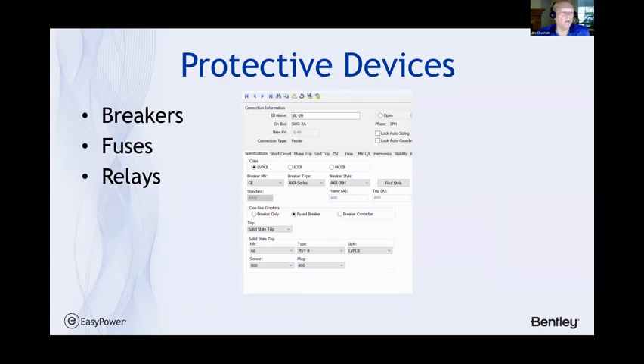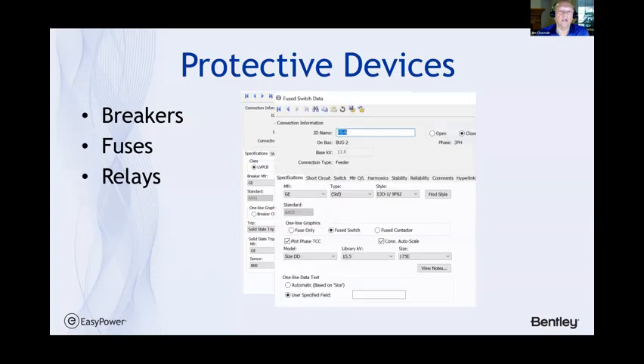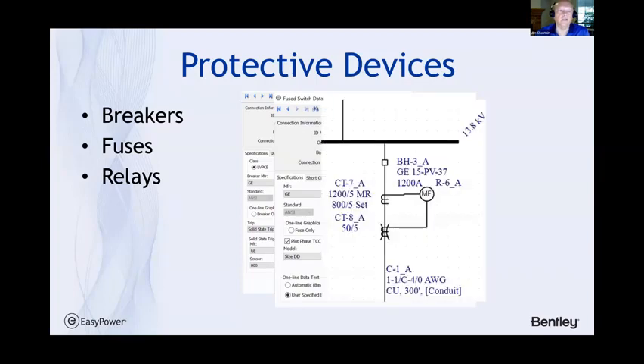One of the things that I harp on during the workshop is how important the time of the arc to extinguish is, and the elements that control that are referred to as protective devices, which include breakers, fuses, and relays. So the details as far as the manufacturer's data sheet, which are all included in the software, have to be included in the data collection process. This includes fuses and relays and the set points and all the manufacturer's designation for utilizing that as a safety device.